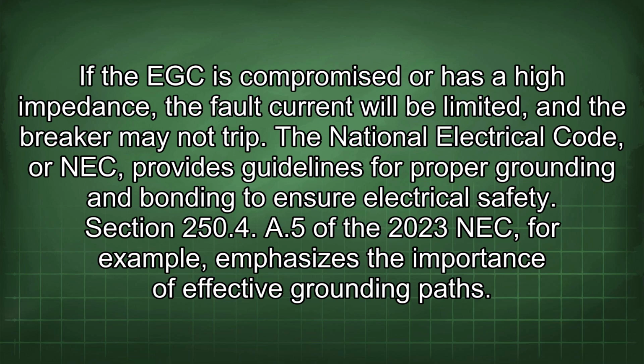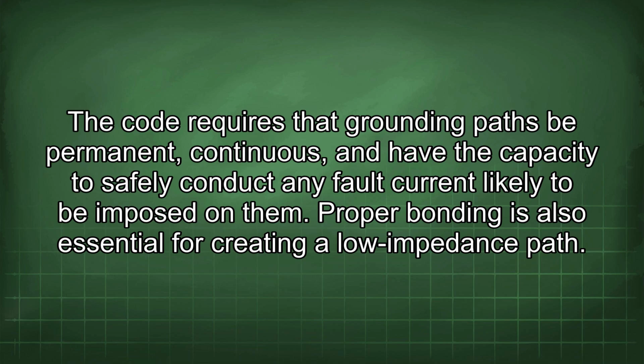The National Electrical Code, or NEC, provides guidelines for proper grounding and bonding to ensure electrical safety. Section 250.4(A)(5) of the 2023 NEC, for example, emphasizes the importance of effective grounding paths. The code requires that grounding paths be permanent, continuous, and have the capacity to safely conduct any fault current likely to be imposed on them.